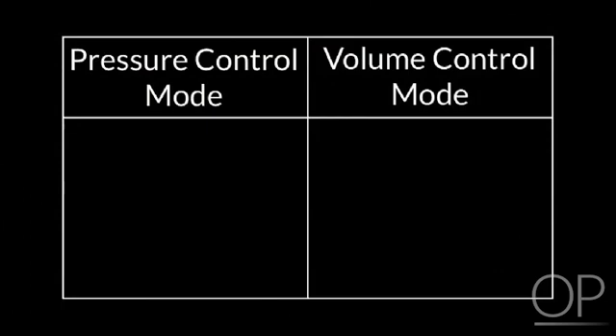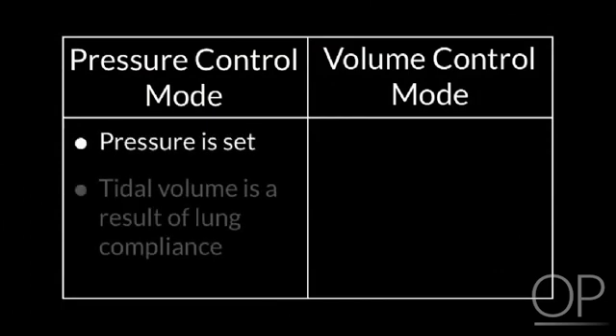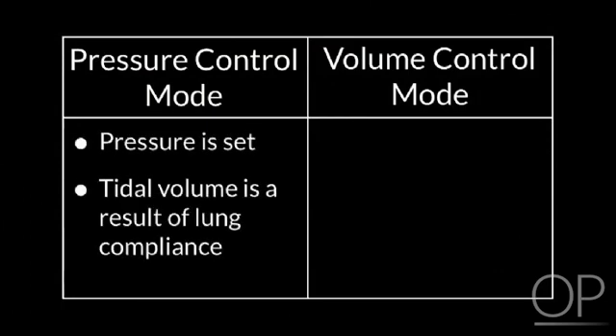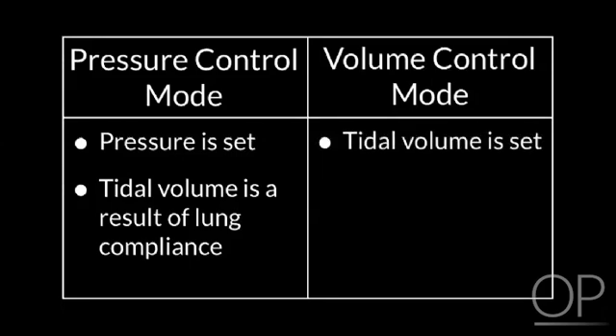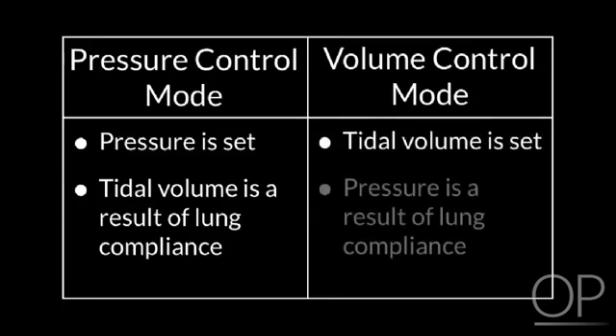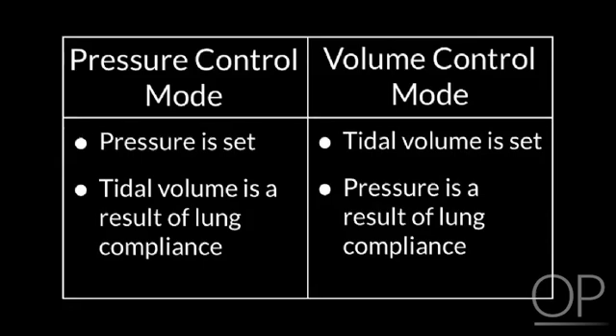Pressure control versus volume control — what's the difference? In pressure control, the pressure is set, and the volume the patient receives is a result of his lung compliance. In volume control, it's the other way around: a certain volume is set, for example an inspiratory volume of 500 cc, and the pressure required to deliver that volume is then a result of the patient's compliance. The important difference between both is the shape of the inspiratory flow.